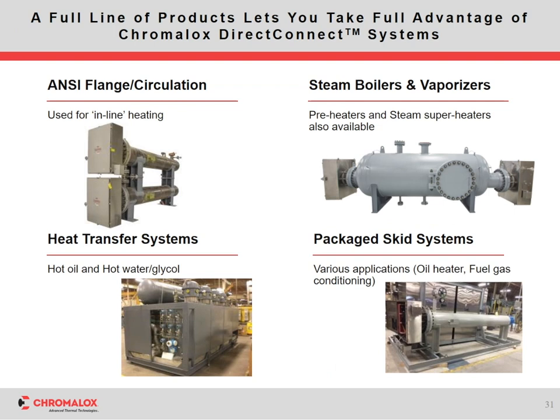Now, Chromalox offers DirectConnect technology in a medium voltage system. That technology can apply to a variety of products depending on your application. These are just some of the traditional ones that you would see in the industry. So sometimes a flange or circulation heater. Those are used for inline heating, like we saw on the offshore platform. Steam boilers and vaporizers are another application with large loading. The first case study we ran through was for a hot oil system, but hot oil or water glycol is an application that's very common in industry. And then there's also a wide variety of packaged skids where we'd want to put the heater or fuel gas conditioning panels on one skidded platform to be installed on site.